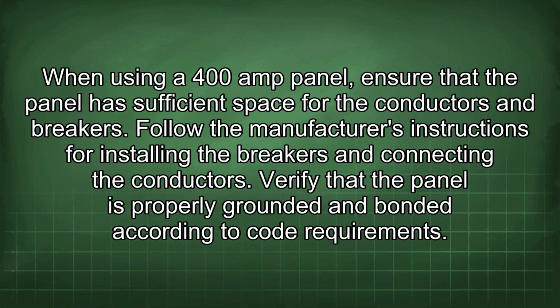When using a 400 amp panel, ensure that the panel has sufficient space for the conductors and breakers. Follow the manufacturer's instructions for installing the breakers and connecting the conductors. Verify that the panel is properly grounded and bonded according to code requirements.